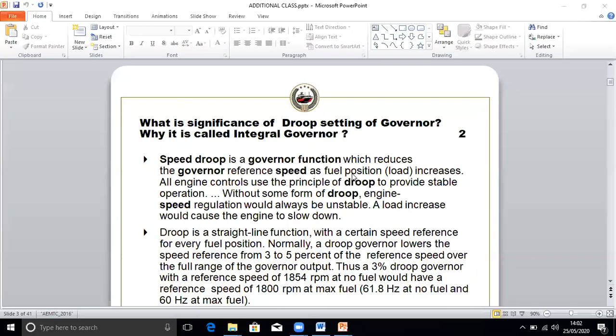Okay. So when the load on the power system is increased, the load current will increase. This increase in armature current will result in an increase in magnetic field on the armature, and the rotor located in the armature field will experience a more attractive force. Means it will try to pull the rotor more, which will reduce the speed of the rotor, and in turn reduces the voltage. So as the speed reduces, the frequency in the system also reduces.